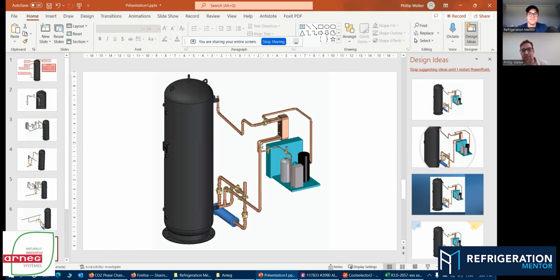So you can see the outlet goes back into our liquid line. Piped a little bit differently than maybe what a lot of people are used to. This is a 1 horsepower pump, and it goes through the plate heat exchanger. We're going to run this around 30 to 32 degrees Fahrenheit, because we're trying to maintain about 40 degrees Fahrenheit at the moment.